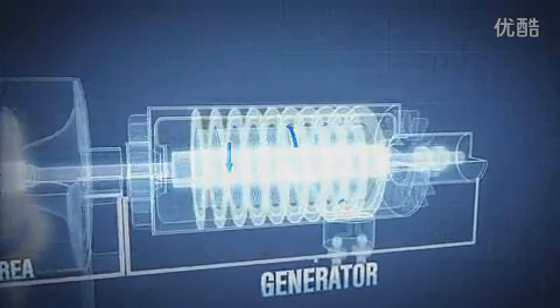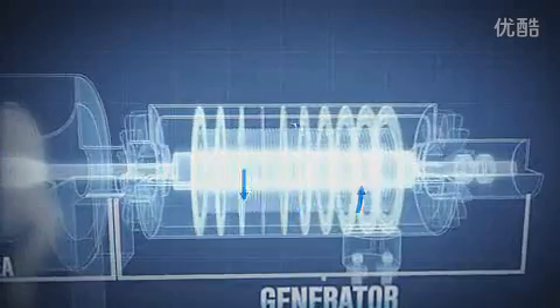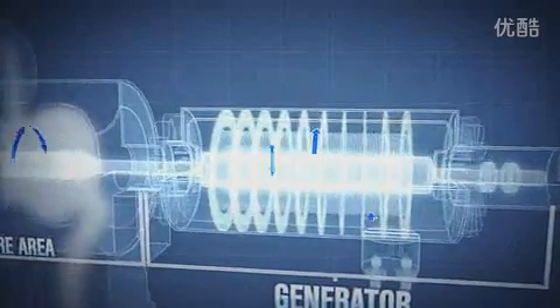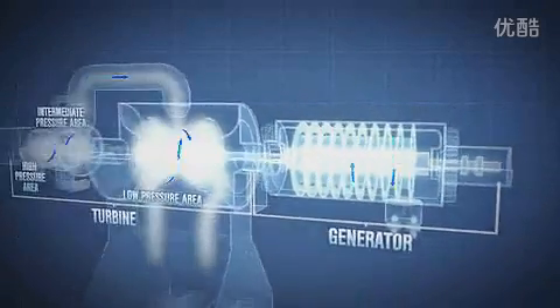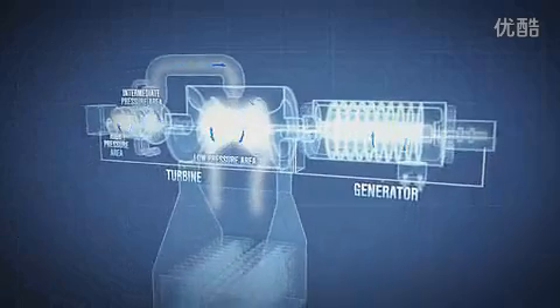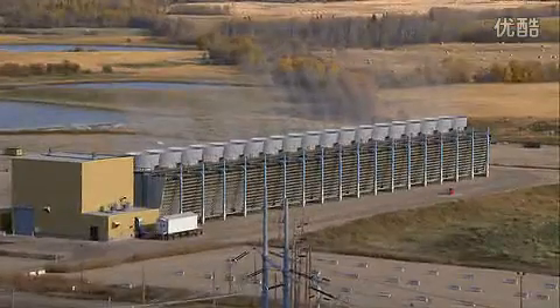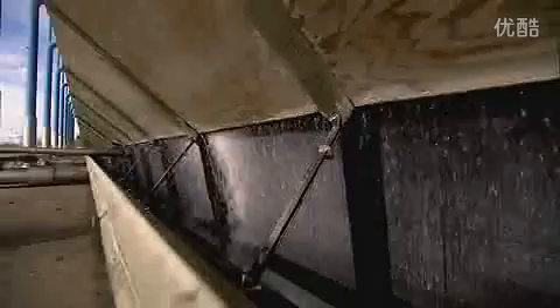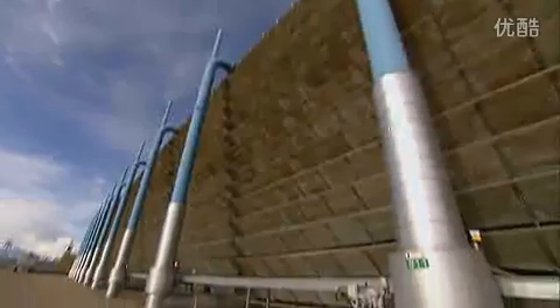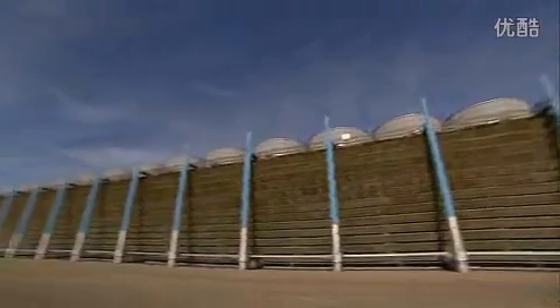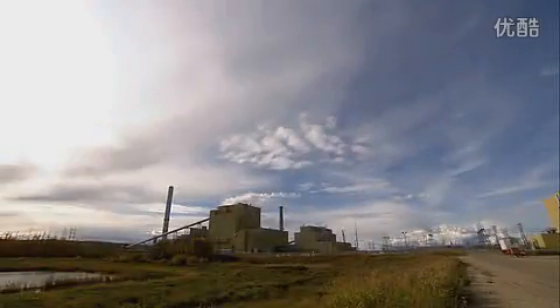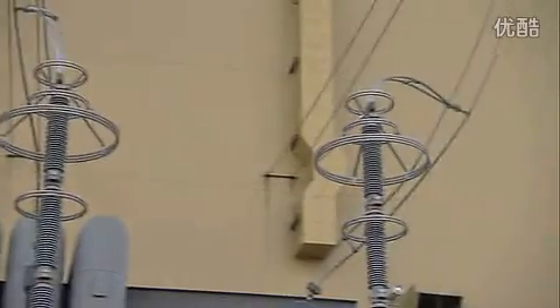This ultra-high velocity spinning turbine shaft creates mechanical power, which drives the generator. The generator converts this mechanical power into electrical power. A cooling water system protects the equipment by circulating water in a continuous loop, from a cooling tower, a large structure that works like a car radiator, to the equipment to remove heat. Electricity is now ready to be output.